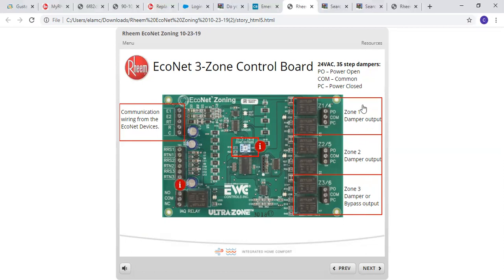Over here you have three zones: Zone 1, Zone 2, Zone 3. You have 3 connections here: power open, common, and power closed. You cannot use 2-wire dampers with this system. It's a fully modulating zone system, so you have to use a power open and power closed 3-wire damper. And they do recommend that you use the EWC brand dampers.